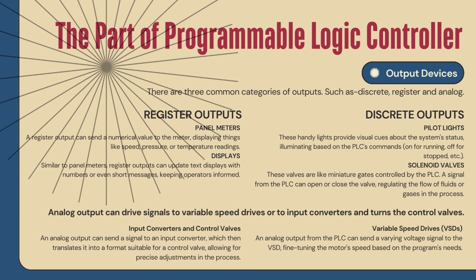The next category is discrete outputs. These are used to control the on and off, or binary, states of devices and components in the system. The first example includes pilot lights, which indicate that a particular status, component, or process is functioning, for example that a motor is running or a valve is open. The next example is solenoid valves, which control the flow of fluids such as water, oil, and air by energizing or de-energizing the solenoid.